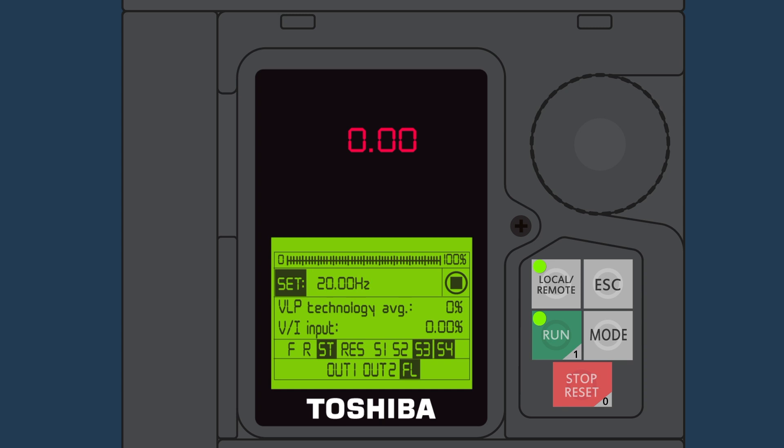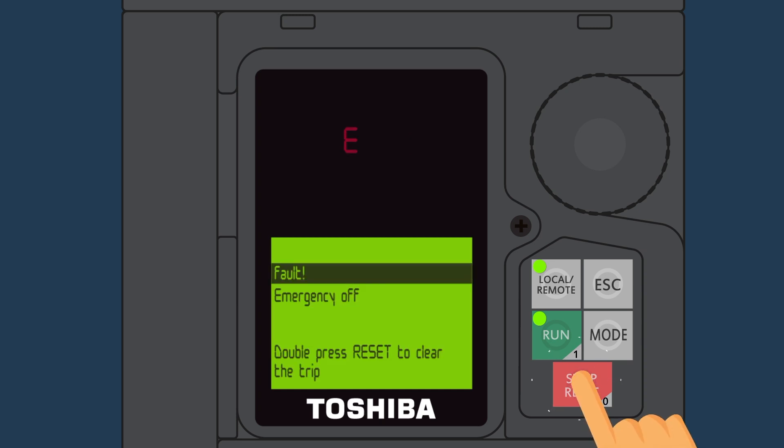Two, initiates an emergency off command if pressed twice quickly. Regardless if you're in the local or remote mode, the emergency off function will either ramp or coast the motor to stop, depending on how the VFD is programmed.